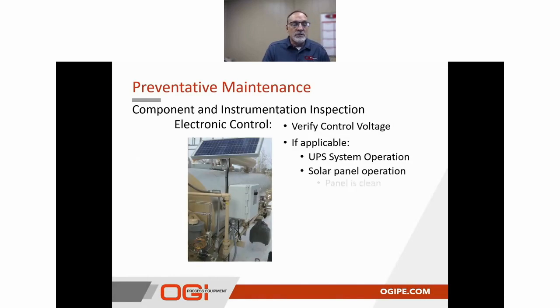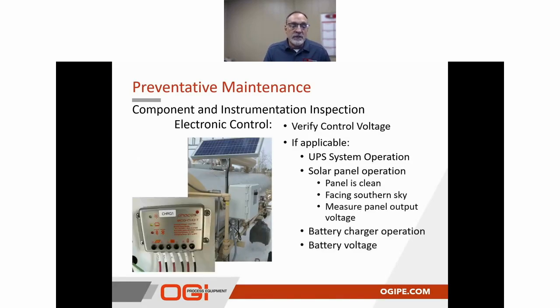Additionally, in electronic control systems, we want to verify that the control voltages are correct. Especially in the case of UPS systems or solar power systems, we want to make sure that each of those components is working, that the output voltages from the batteries are correct, and that the solar panel charge levels are good. In the case of the solar panel, we want to make sure that the panel is clean, because if it's covered with debris or even snow, it will not charge the battery properly.